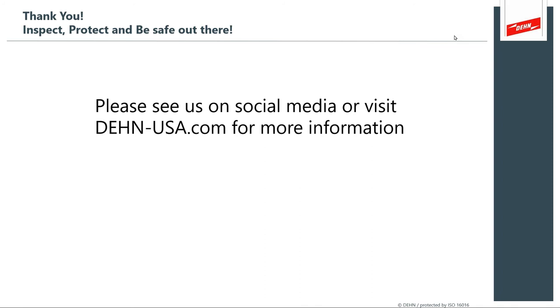Another question: do we need specific earthing beside the lightning protection? The beauty of the system is that it's field deployable — however the tower is already earthed is suitable. That's an interesting question because it can lead to other analysis. If you know you're getting extremely high surge lightning events, it will give you an indication of whether or not your earthing is sufficient, providing more diagnostic tools for design and future upgrades at the site.